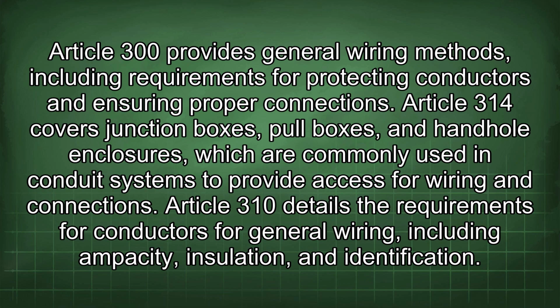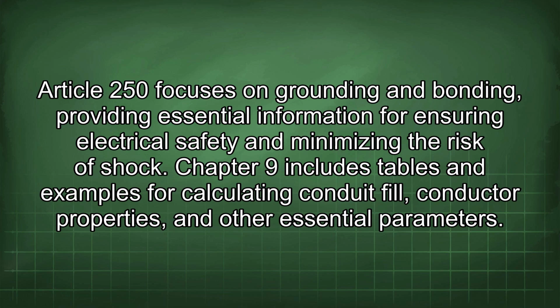Article 314 covers junction boxes, pull boxes, and handhole enclosures, which are commonly used in conduit systems to provide access for wiring and connections. Article 310 details the requirements for conductors for general wiring, including ampacity, insulation, and identification. Article 250 focuses on grounding and bonding, providing essential information for ensuring electrical safety and minimizing the risk of shock. Chapter 9 includes tables and examples for calculating conduit fill, conductor properties, and other essential parameters.